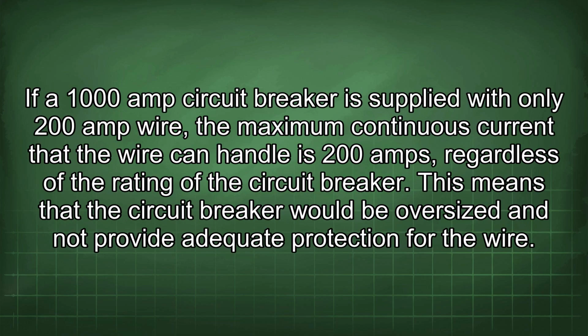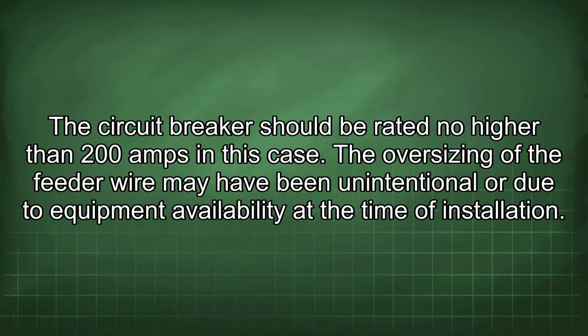If a 1000 amp circuit breaker is supplied with only 200 amp wire, the maximum continuous current that the wire can handle is 200 amps, regardless of the rating of the circuit breaker. This means that the circuit breaker would be oversized and not provide adequate protection for the wire. The circuit breaker should be rated no higher than 200 amps in this case.